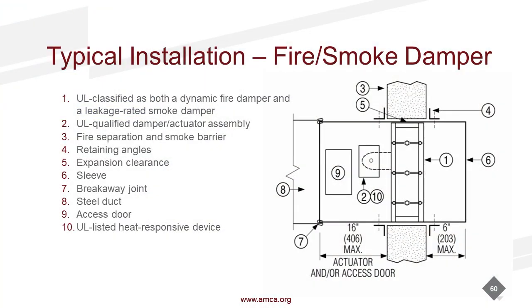Every once in a while, you'll get an owner or a building inspector that says, hey, that's a big hole around the damper. We see that when we put single-sided angles on. One side looks finished. It has a retaining angle, looks clean. The back side has no angle and has a gap around the damper. So it just, intuitively, you think that's not right. It is. But a lot of times we get building inspectors and owners that say, put some material, put some fire stop material, put some putty, that is a no-no. Do not fill the gap. There is a specific installation for fire stop caulking. You have to follow those instructions if you want to caulk using a retaining clip installation, not a retaining angle installation.